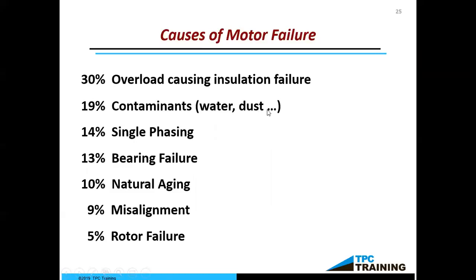And so I would love to have a vacuum around. We vacuum things out. If we do lose a phase, that's going to cause circulating currents in my motor. That's going to cause extra heat, cause the motor to fail. Same with the bearing. If the motor is turning harder than it should be, cause extra heat for us, motor will fail. Or just natural aging or misalignment, rotor failure.